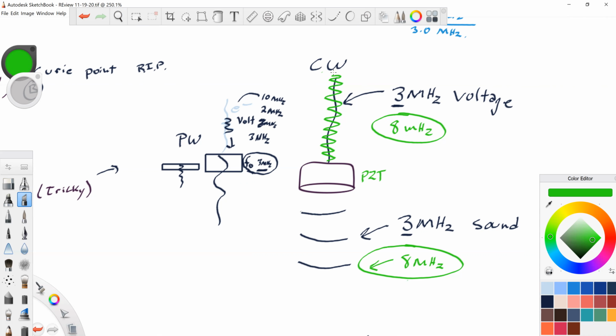So continuous wave transducers, whatever voltage you hit them with is the sound that it creates. I will say, and this is not part of the book, so take this with a grain of salt, you're not going to hit an extremely thick element with an extremely high frequency voltage and vice versa. So there is some tuning involved, but there's a lot more leeway with continuous wave. Back to this guy over here. Just remember, this guy is struck once, quickly, and then allowed to ring on its own. And so that is why the wavelength is created more by the element in pulse wave. Okay.